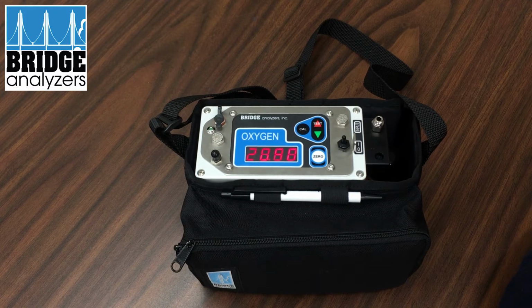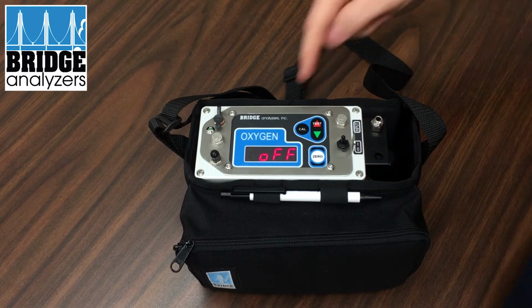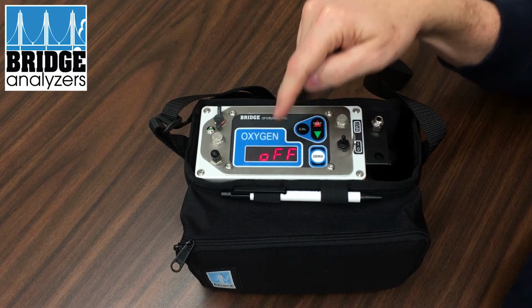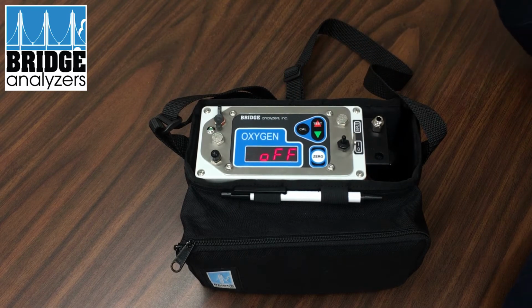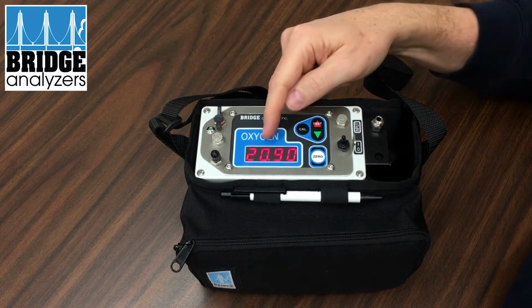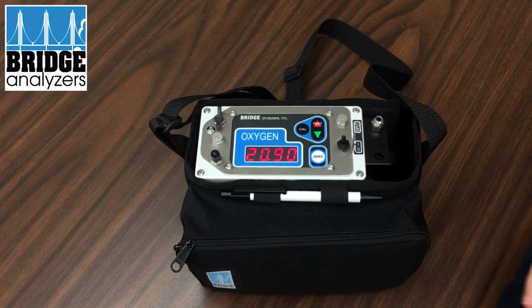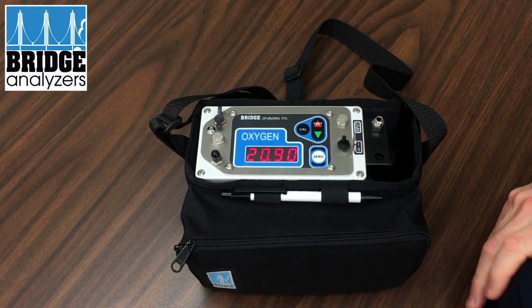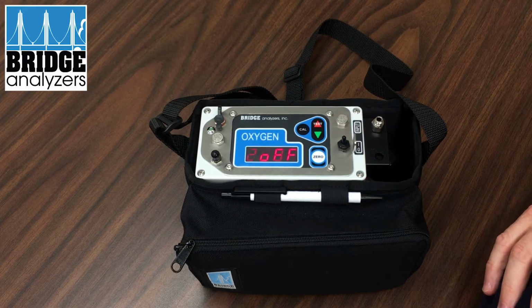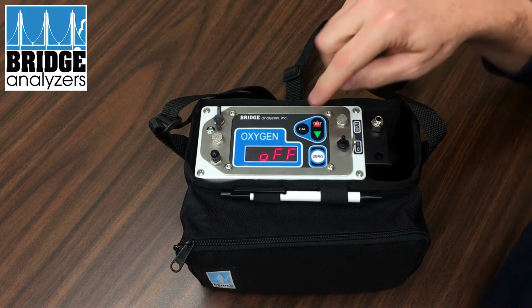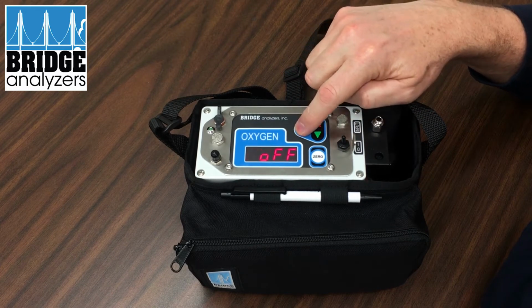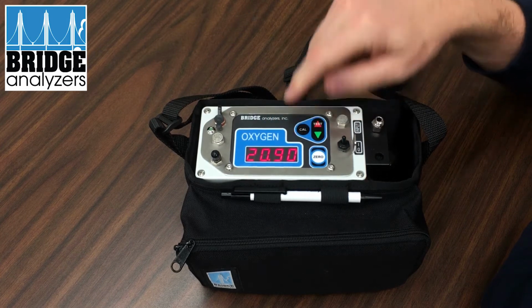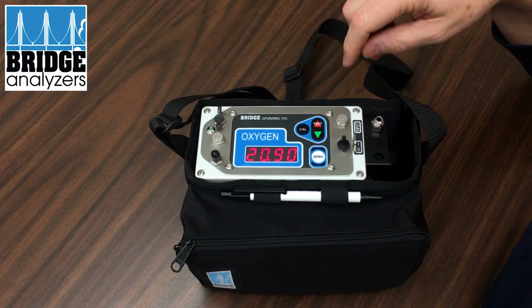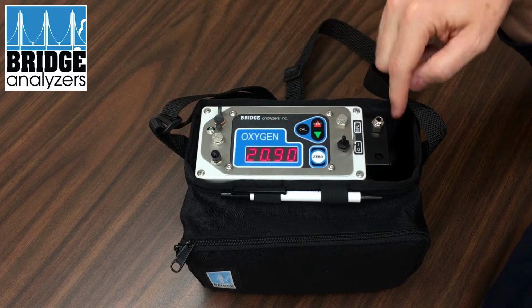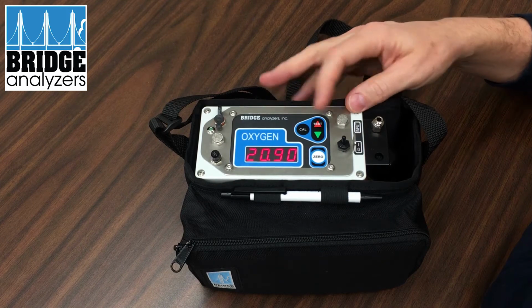In this case, when the analyzer is nearly exhausted in its life, it will blink a low and then the oxygen reading. And then once it has fully expired, it will blink off and then the number, which is the oxygen reading. When it's blinking off, you're not going to get reliable results on any testing that you're doing. If you press any of the buttons on the display, the off will go away and that warning message will be gone. So when you see off, there is an easy way to replace the oxygen sensor.